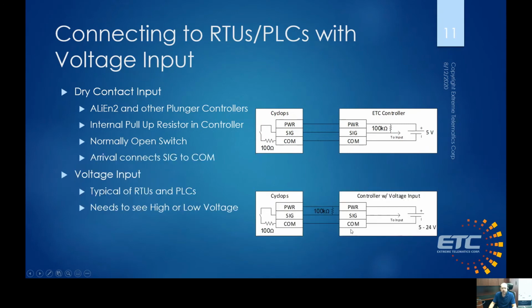On a voltage input, though, it's expecting a voltage all the time. And so it needs to see a high or a low voltage coming into the RTU or the PLC. And like I said, with Cyclops or Sasquatch, the switch is open when there's no plunger present or no plunger has arrived. And so you get an indeterminate value. That undefined value can confuse these PLCs and RTUs because they don't know if it's high or low, and it's essentially floating. And so you can get premature arrivals when there's no arrival actually present.